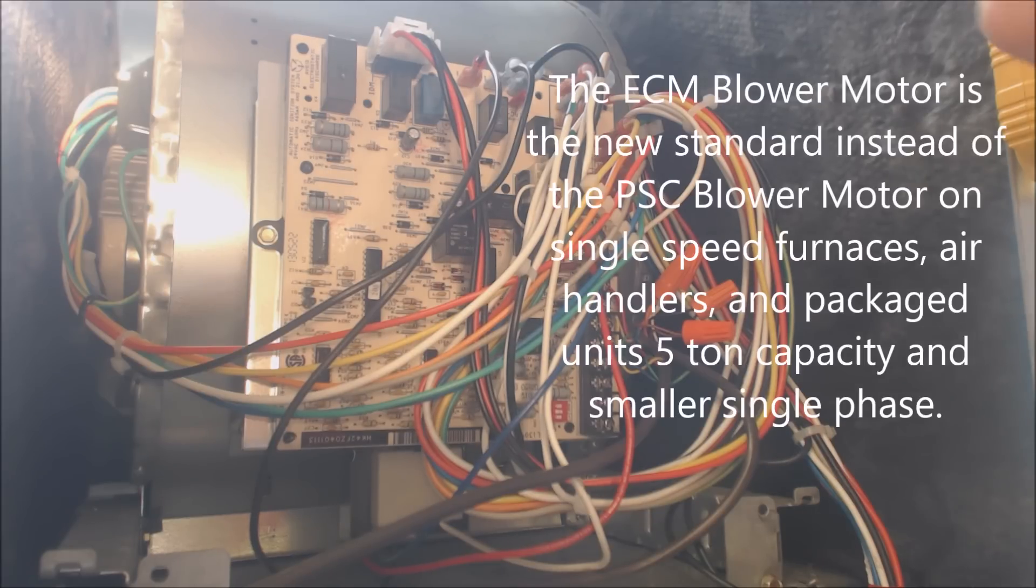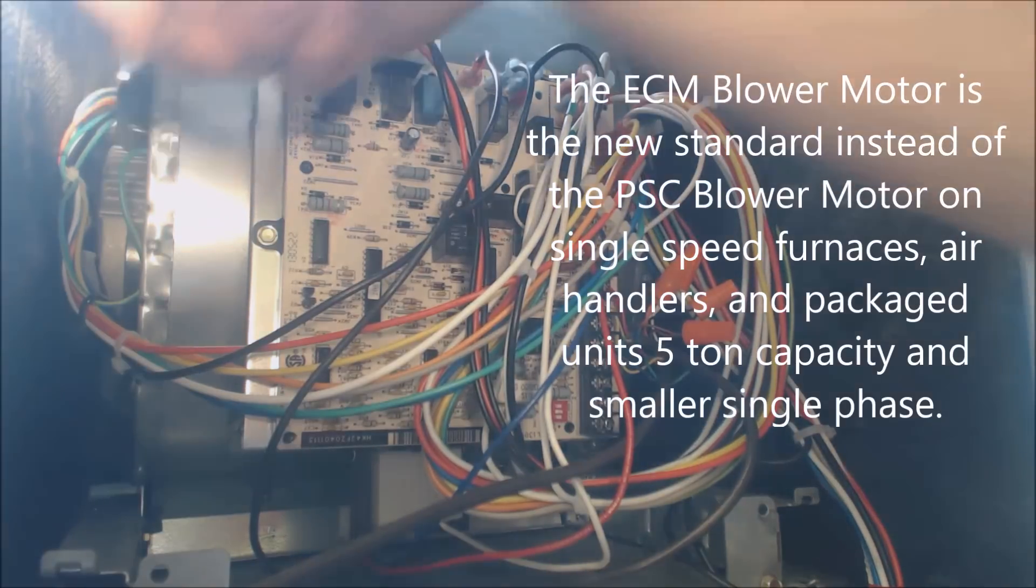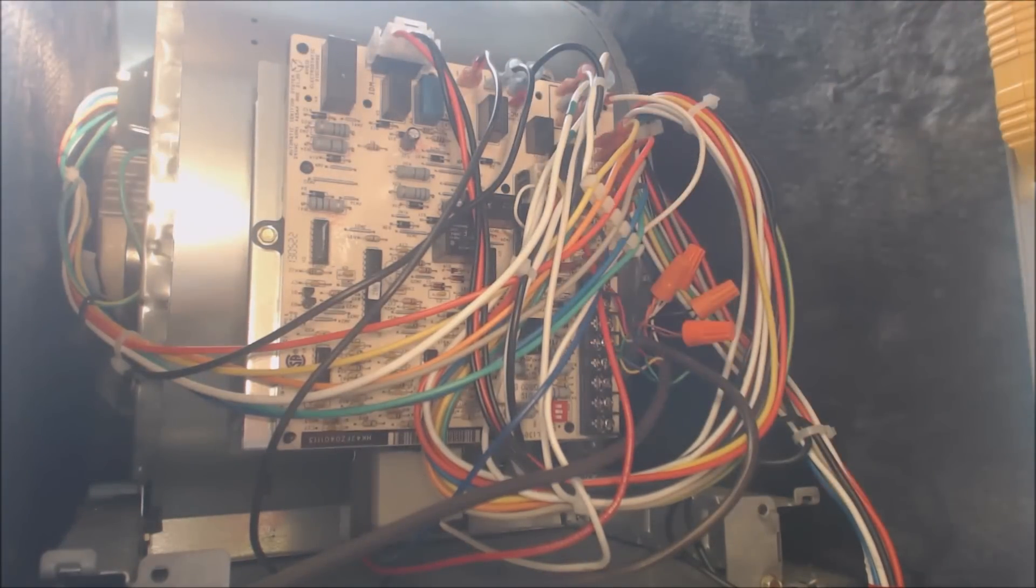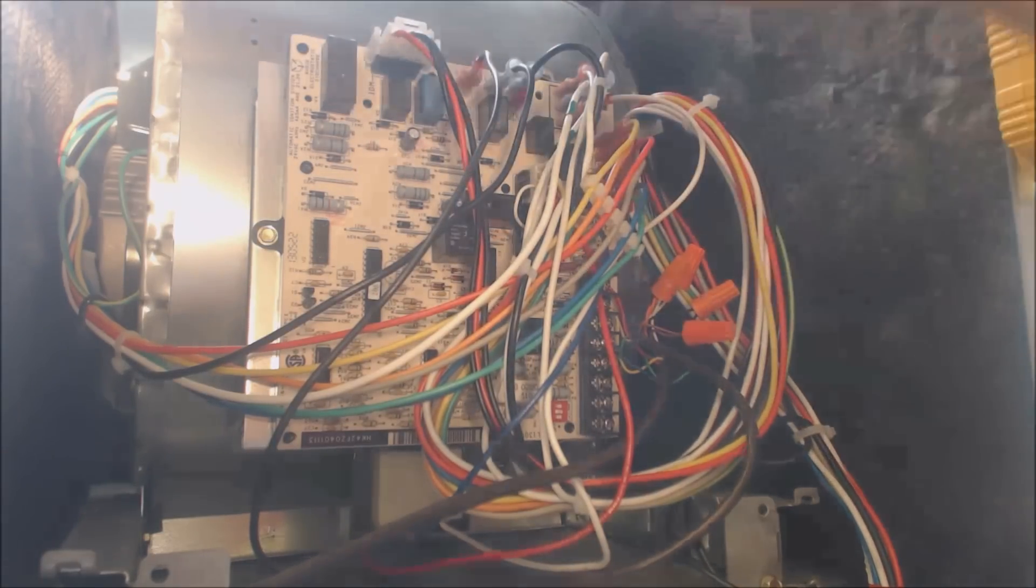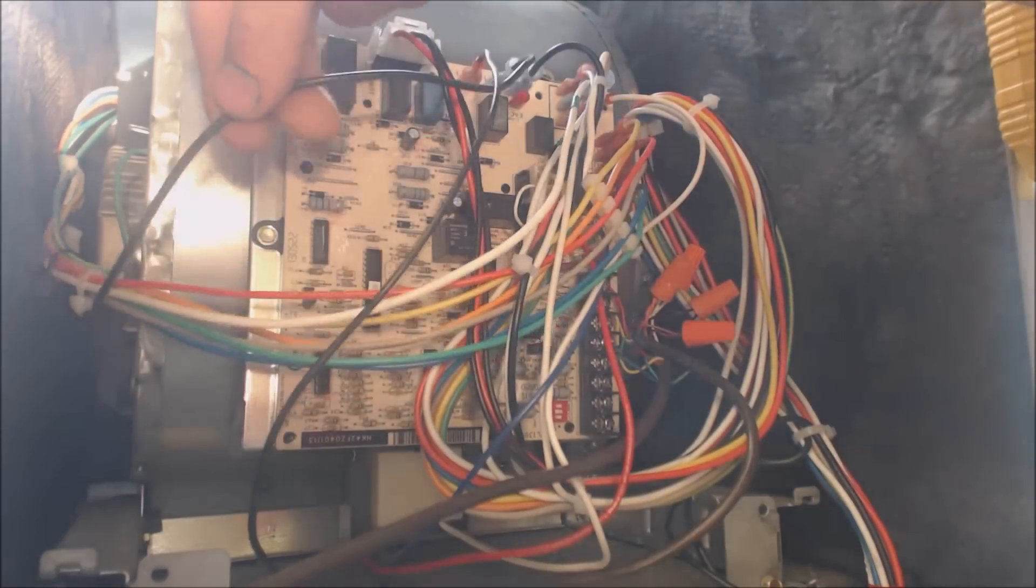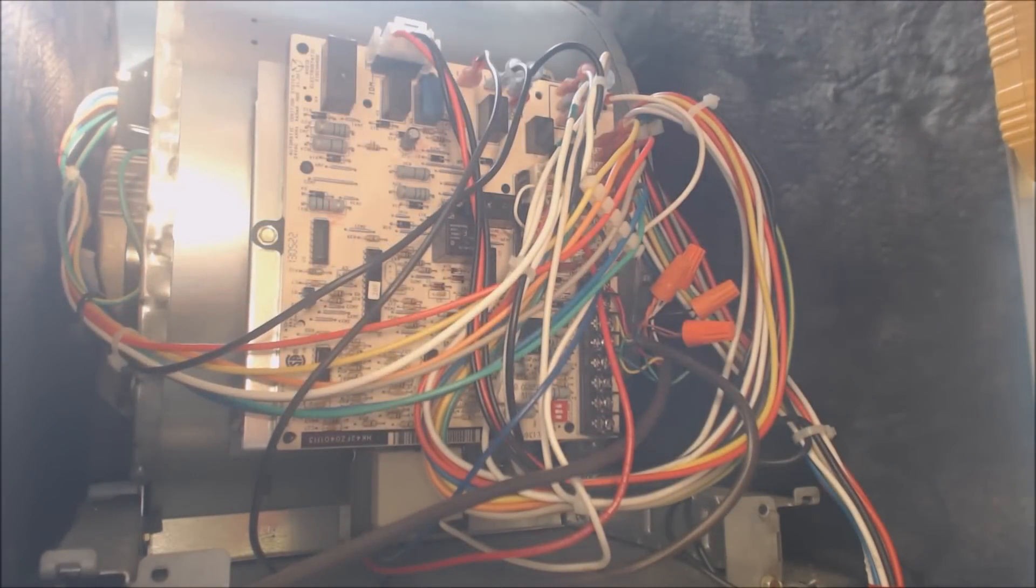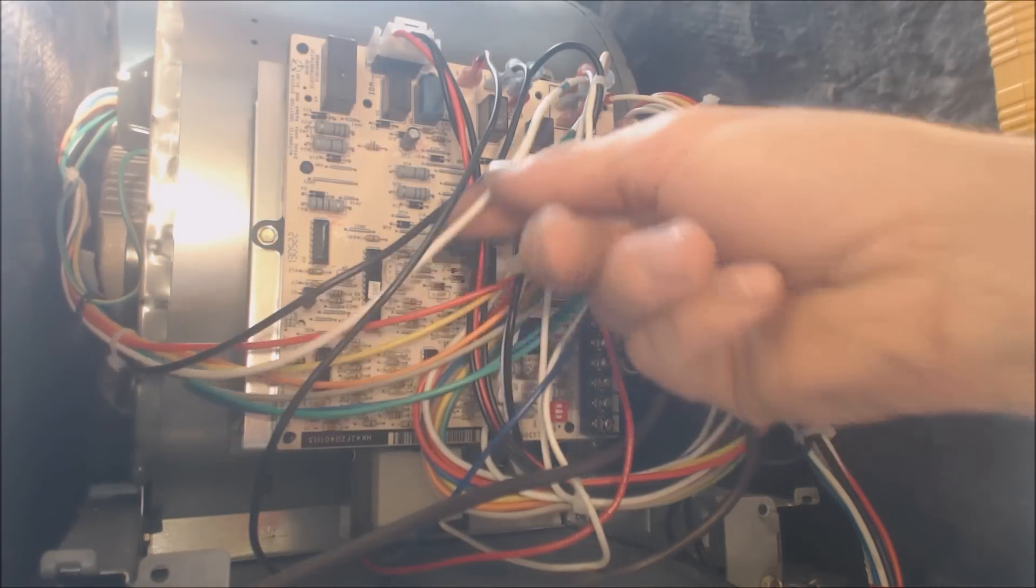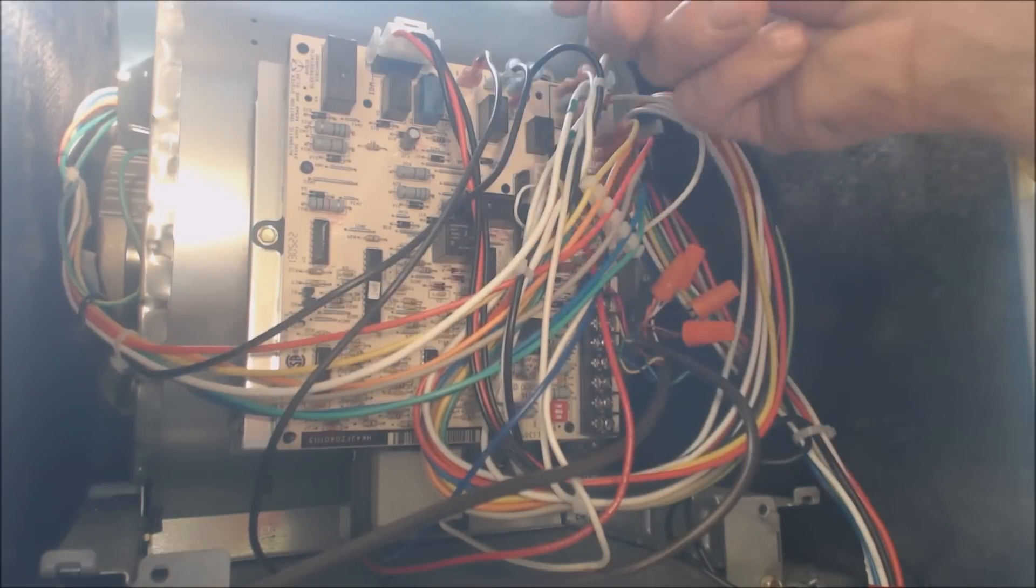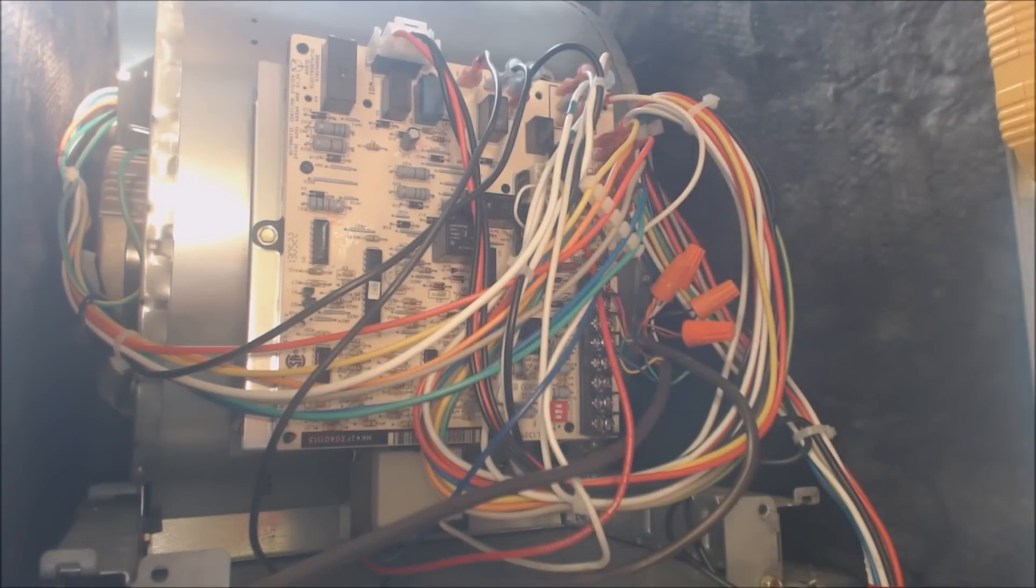It's important to know that there's power going to the blower motor at all times, the 120 volts in this case because it's a furnace. So whether this blower motor is on or off, there is 120 volts. This wire right here, the black on this control board is actually BL-1 and then you have your common that's going to the L2 common neutral bar.